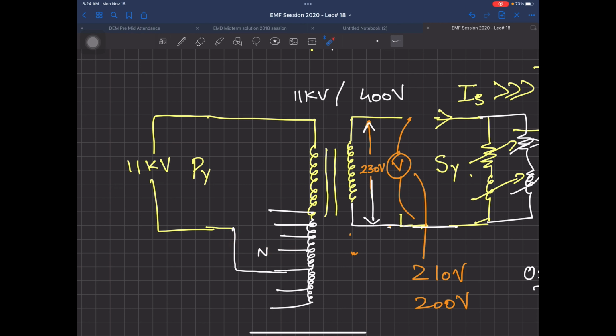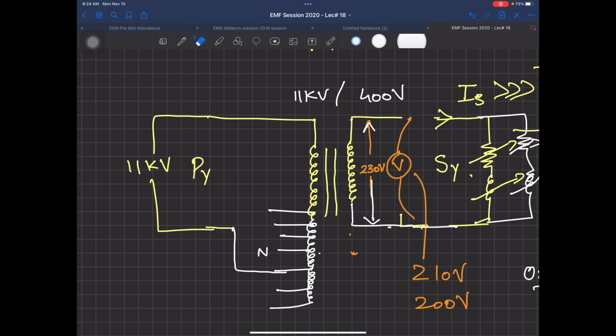Normally these taps are arranged so that one is called neutral, the next plus 2.5%, then plus 5%, then plus 7.5%. On the other side, minus 2.5%, minus 5%, and minus 7.5%. These percentages represent how much your voltage is going to change.